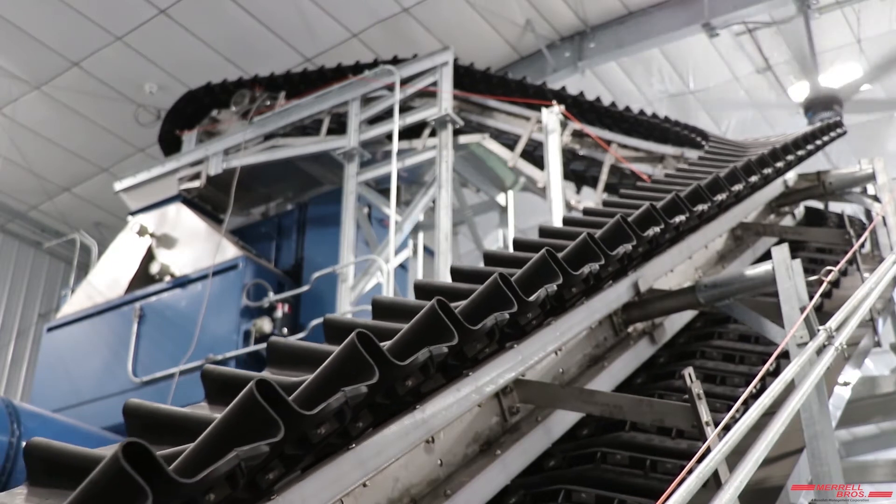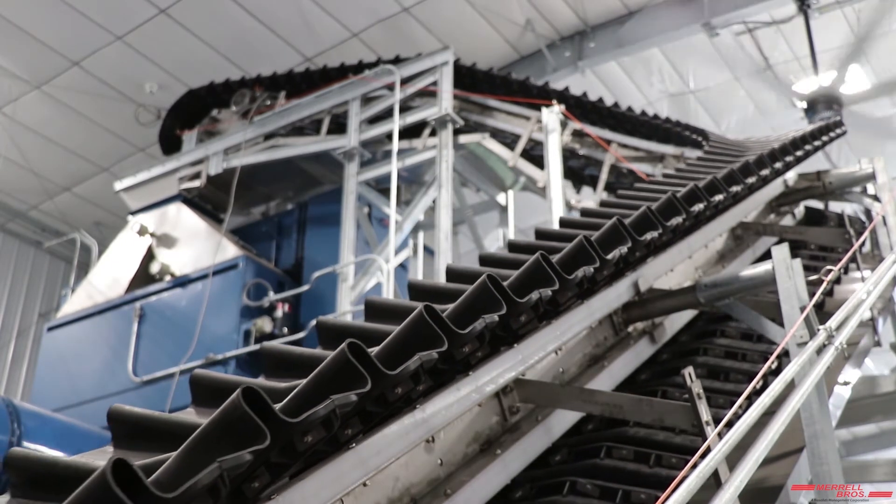From the day hopper, material goes onto another Serpentex conveyor that winds up and drops the material into a slightly modified belt dryer. The top chamber — our heat-up chamber — places biosolids two to three inches thick on the belt and forces hot air up through the material, creating a fluid bed. Air is blown through at 30,000 CFMs, making the biosolids dance on the belt, ensuring even heating. We're preheating the biosolids in a single-pass operation from ambient temperature up to 70 degrees C (158 degrees Fahrenheit).